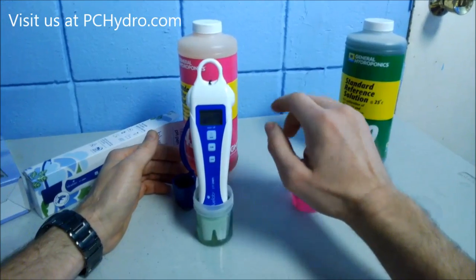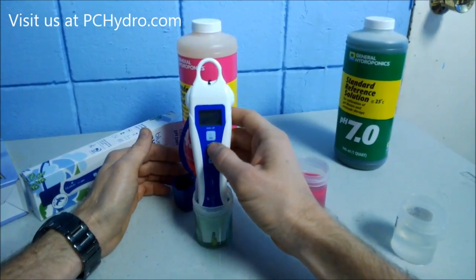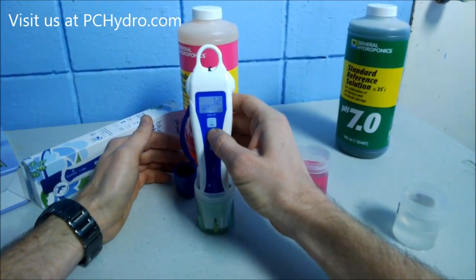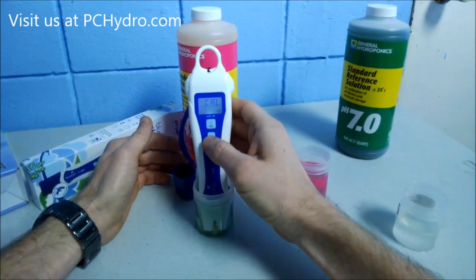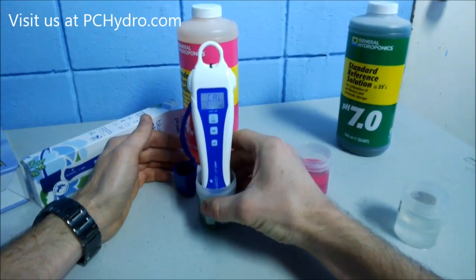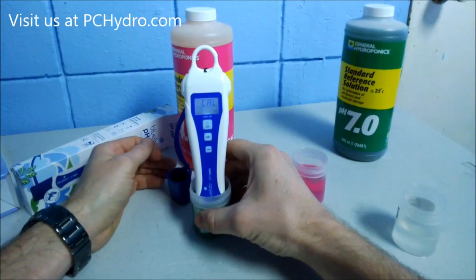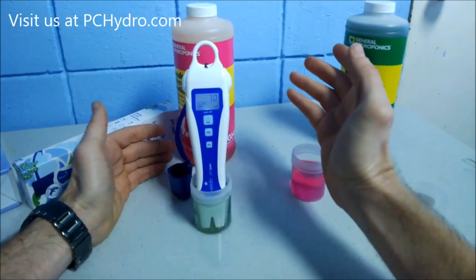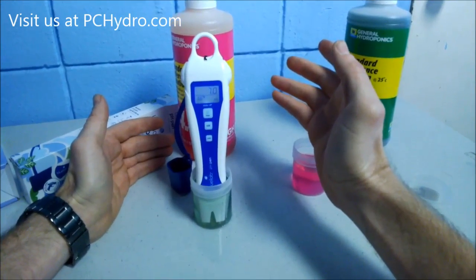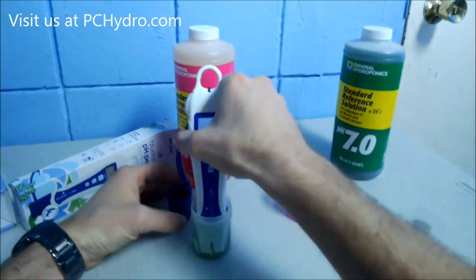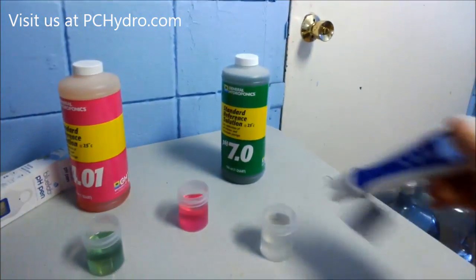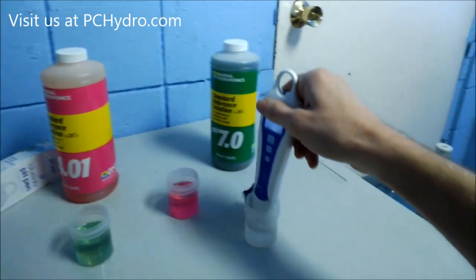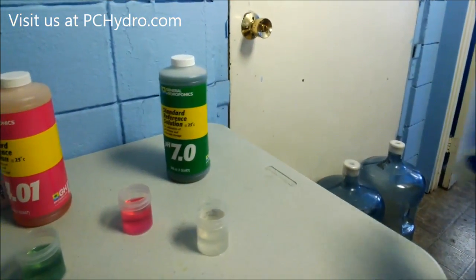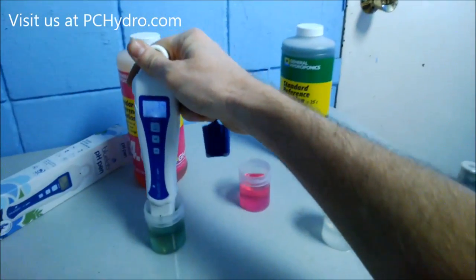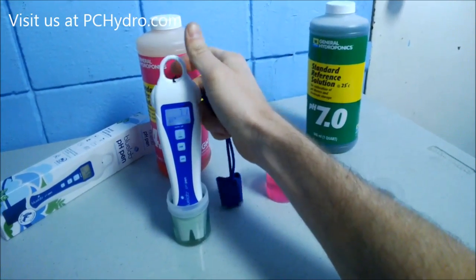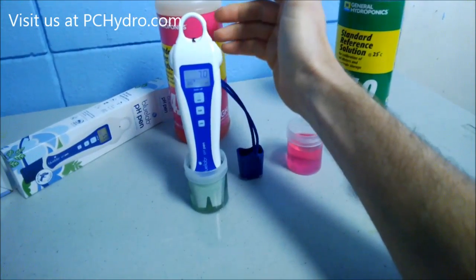Now, it's reading 7.2 actually, and we're just going to hold the cal button down, and it's going to start flashing cal, and that's going to take it to 7. And it says 7 right there on the pen, and it's a 1-point calibration, and that's all. It's now calibrated to 7.0, and if we take it out and rinse it off in our other solution here, and put it back into the 7, it should just read 7 pretty quickly. And there it is, read 7.